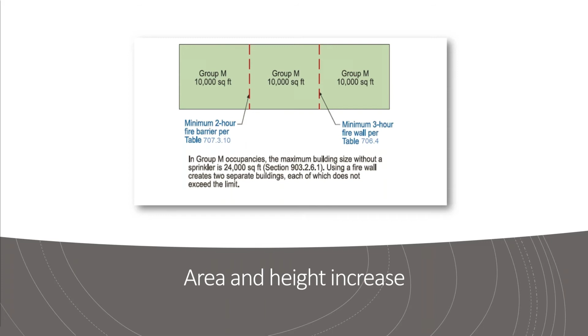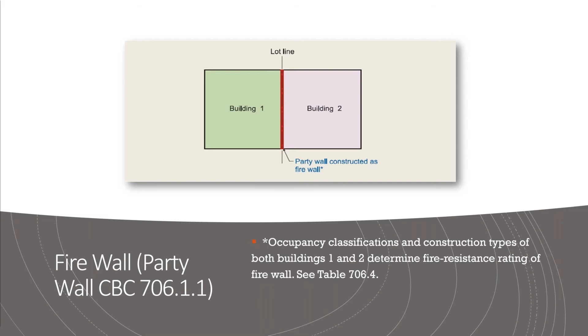And then a party wall. So this is the other. This is a firewall that's constructed as a party wall, constructed as a firewall. This is the example for when you've got a true deeded lot line between the 2 different buildings. And then you obviously have to look at the occupancy classifications and construction types of both buildings 1 and 2 in order to determine what hourly rating that wall has to be, and then go to 706.4 to figure that out.